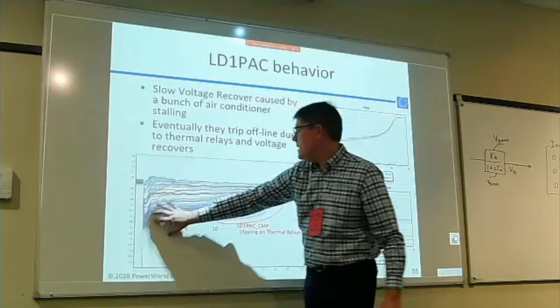load. So this is one of those situations where maybe we need to model the capacitor banks that would trip off to bring the voltage down. Maybe even tap changing transformers might be useful to get rid of these voltage overshoots. 1.2, 1.3 per unit are not unusual. But you have to run it out to 25 seconds or so.